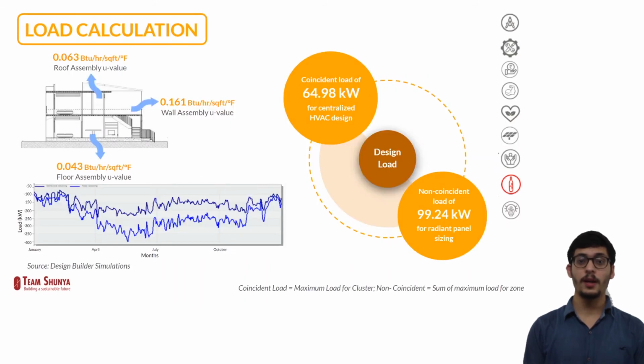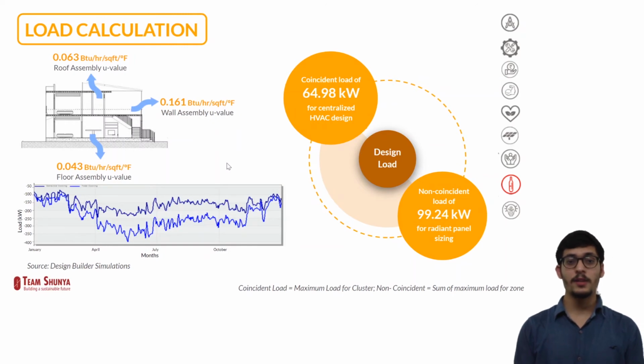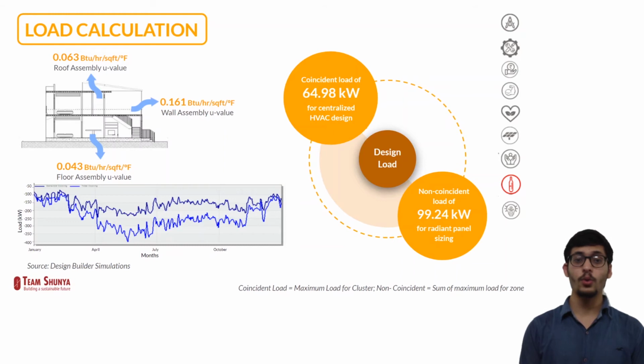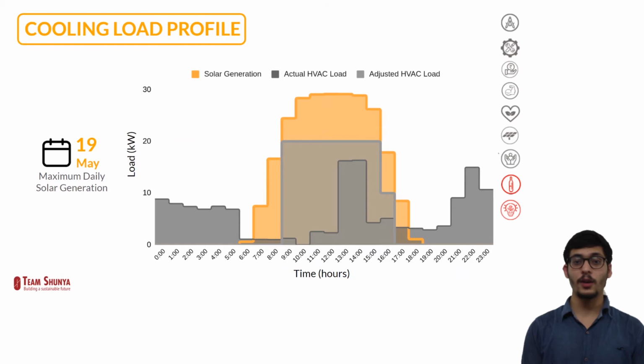Based on various building control layers, we got these optimum U values. We replicated the model in Design Builder software for load calculation, which is useful for HVAC design. Customized scheduling has been done based on survey of the selected locations. From the two output profiles, the coincident load is used for centralized HVAC design and non-coincident load is used for radiant panel sizing.